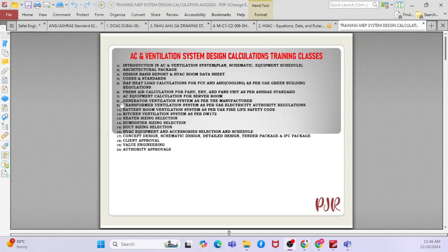Today we will talk about fresh air handling unit capacity calculation: how to calculate the tonnage for the FAHU coils. Last week we saw how to calculate the airflow rate for the fresh air and for the exhaust based on ASHRAE 62.1, based on the different classifications, different rooms, and different occupancy categories.